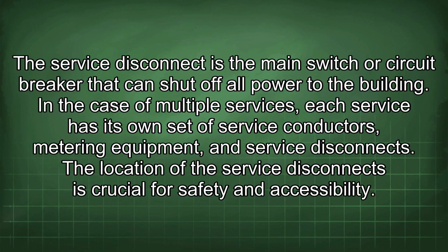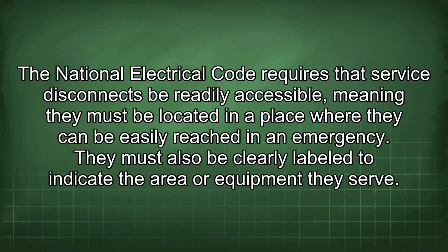In the case of multiple services, each service has its own set of service conductors, metering equipment, and service disconnects. The location of the service disconnects is crucial for safety and accessibility. The National Electrical Code requires that service disconnects be readily accessible, meaning they must be located in a place where they can be easily reached in an emergency. They must also be clearly labeled to indicate the area or equipment they serve.